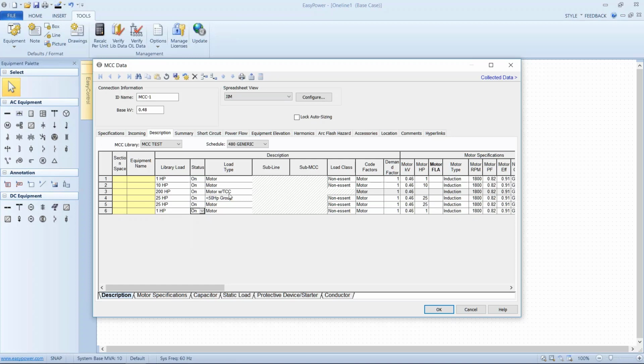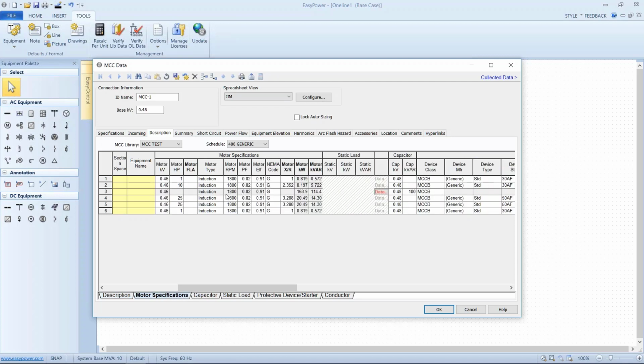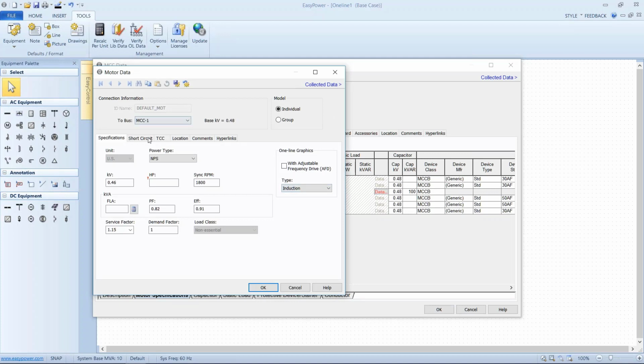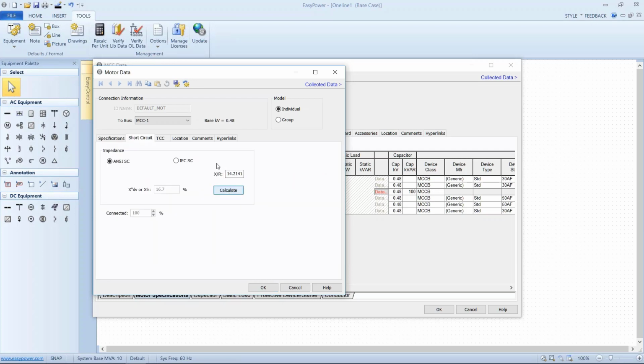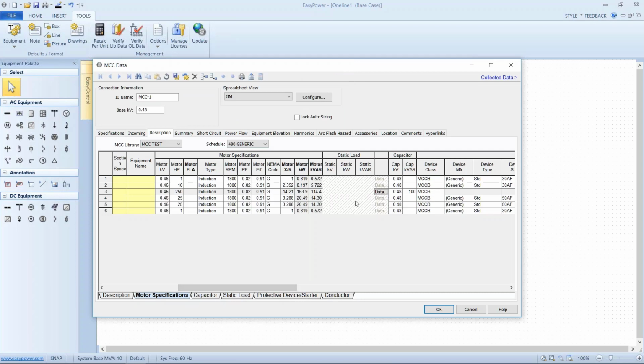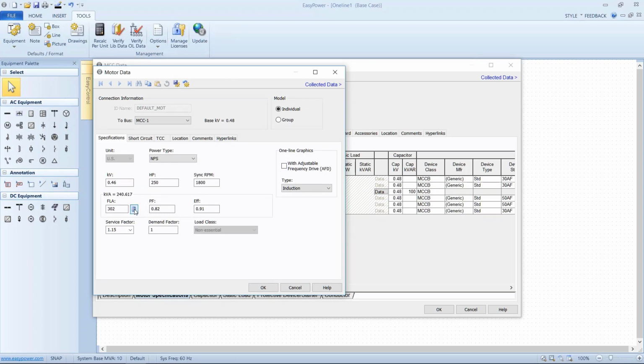Now, the significance of putting in the motor control center load with the TCC. I've designated this even after I put in the size of the motor. If we go over to the motor specifications, we can see that we cannot put in information here. I cannot enter data once I've made that designation, and the data icon over here is flagged red. That means I have to use it to input the size or the parameters for the motor. So let's say this is a 250 horsepower motor, and X over R calculations include short circuit, and I may or may not want to include the full load current, which I'd have to do again back here, thusly.